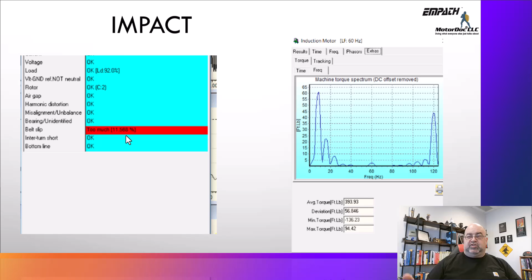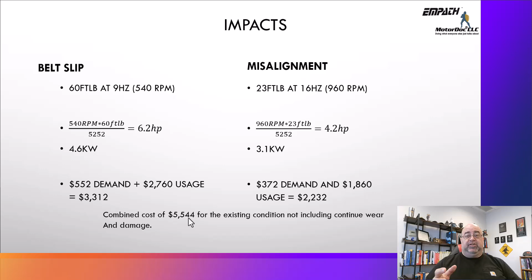So when I take a look at it, I can look at the belt slip in this case, and that comes out to about $3,300 in demand, 4.6 kilowatts; misalignment, 3.1 kilowatts, so that's 22. We're talking about $5,500 in energy costs per year based upon a misaligned and slipping belt. And I love belted applications because I get numbers like this all the time.